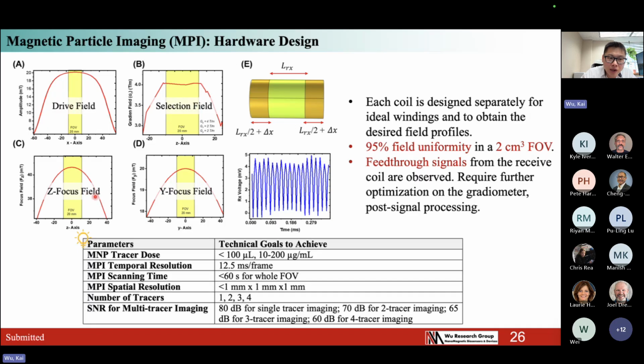These are the slowly changing fields to switch the location of the field-free point in the space. You can see almost 95% field uniformity in the 2 centimeter field of view. So this tells us that this coil design, with the dimensions we entered here, is able to generate a uniform field for 3D scanning in the field of view we want to scan.